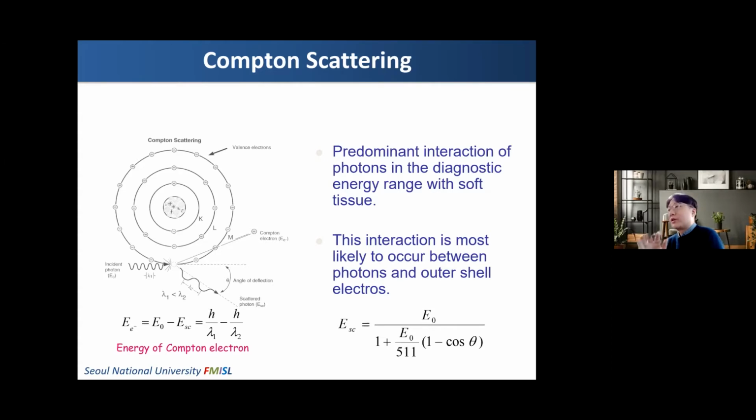So as I told you, the photon changes energy due to this Compton scattering. This is why, in the gamma camera and PET, we apply some energy window. I mean that we apply, for example, a plus or minus 10% energy window around the primary photon peak of each radioisotope to reject these Compton scattered photons based on this energy information.